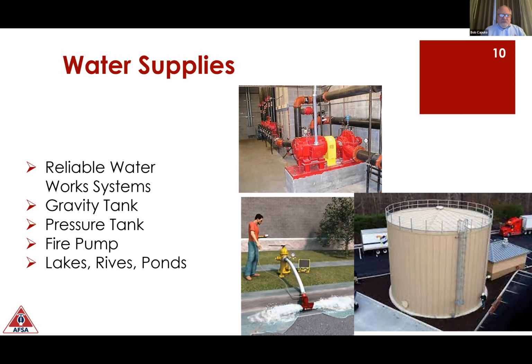So the first thing the designer of a system needs to know is, what's my water supply? Am I going to use the municipal water supply, or is that inadequate for my need for this warehouse use? If I don't have enough pressure, I'm going to add a fire pump. And that fire pump is going to boost the pressure from the city pressure to the pressure that I need for that particular fire sprinkler system. If the volume of water is inadequate, I can add a water storage tank. And of course the fire pump, which in the bottom right picture you see in this little house next to the water storage tank, is going to move the water from the tank to the system and of course impart pressure.